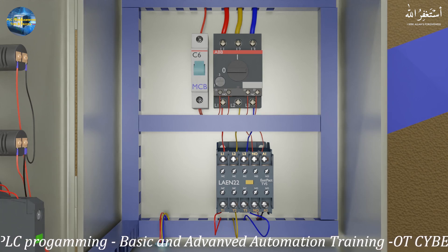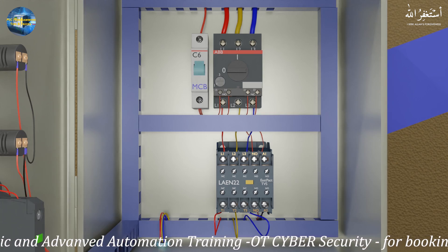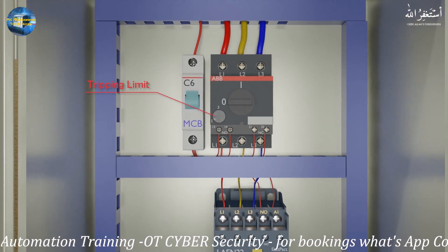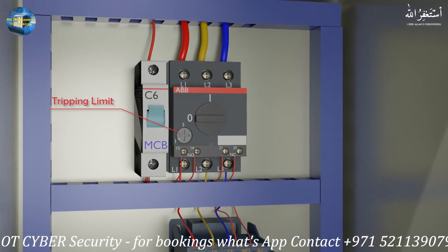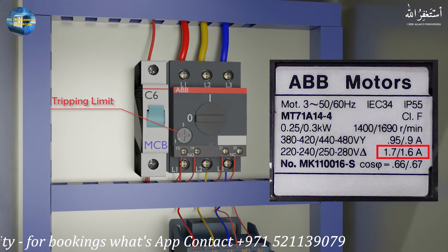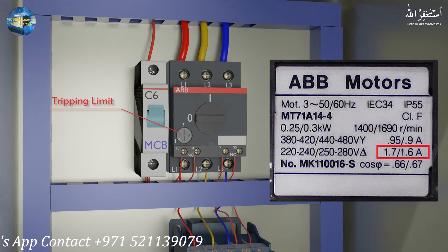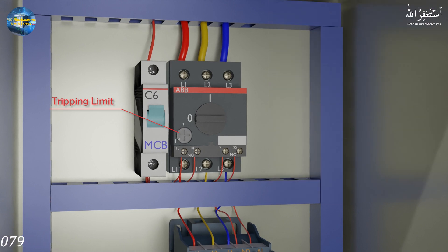First, we can check the motor nameplate and verify the rated amps of the motor. We have to confirm that the tripping limit in the motor protector breaker is set as per the motor nameplate. In our case, the motor rated current is 1.6 amps, so we can set the current limit by rotating this knob using a screwdriver.